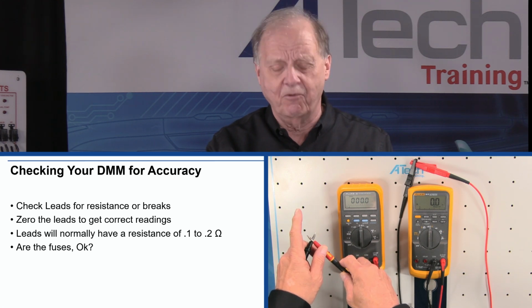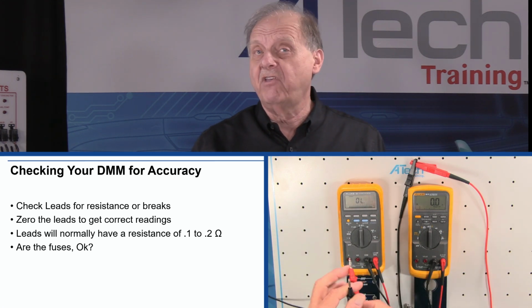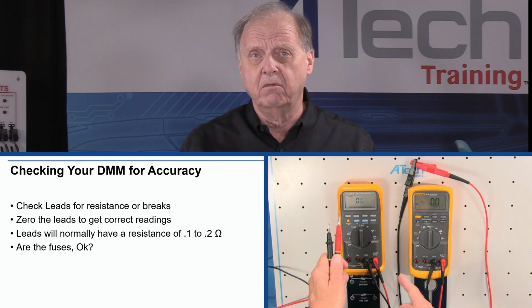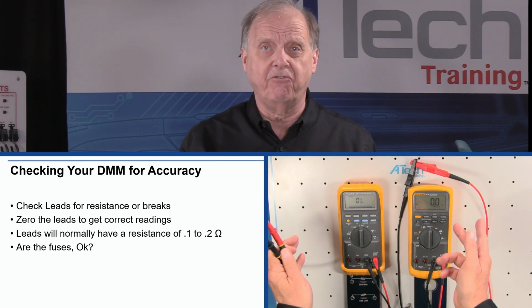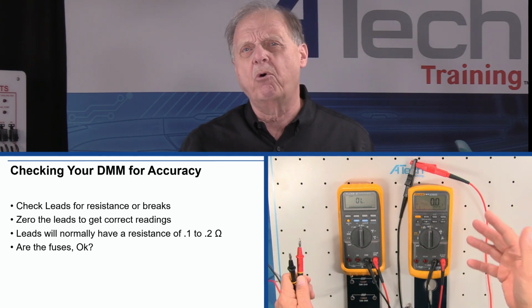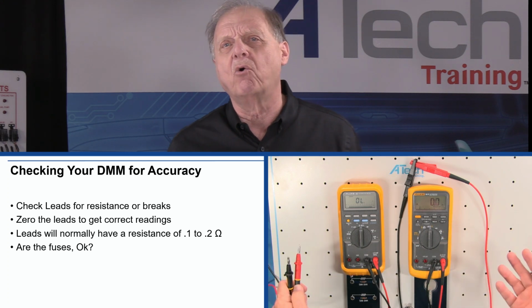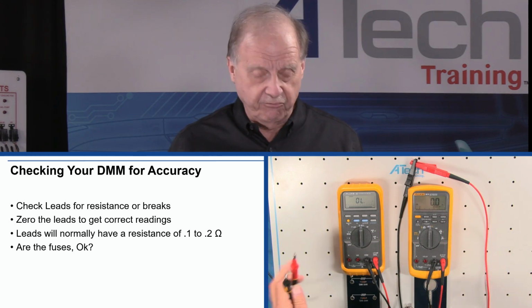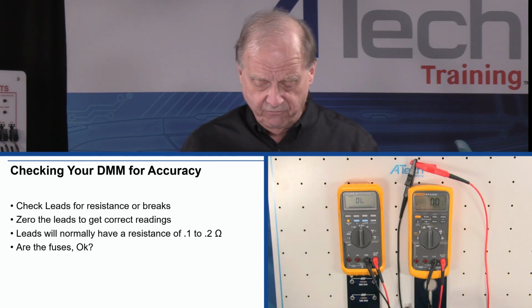So we have to know that our meter leads are working. It tells me two things: my leads are good on both sides because they're less than 0.2. If it's 0.3, 0.4, 0.5 or higher, I would go immediately and think I need to replace my leads. This one shows it's working fine right now.